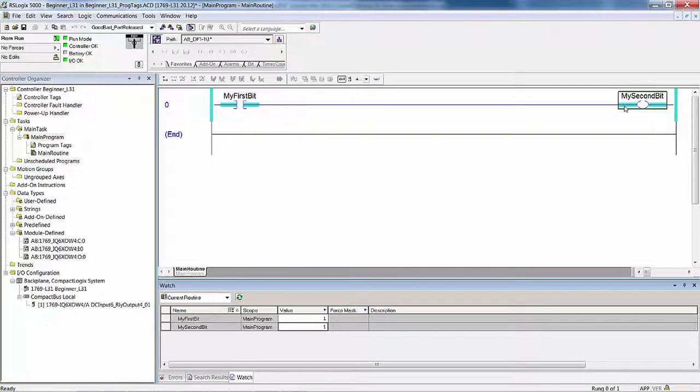There's no ladder logic in the controller. This is just a graphical representation for us. This representation down here, the state of those two memory locations, mirrors this. It's one and the same thing. Did the tag value remain at 0? No. Why? Because we went into the run mode, it executed this rung of logic and set it to 1.